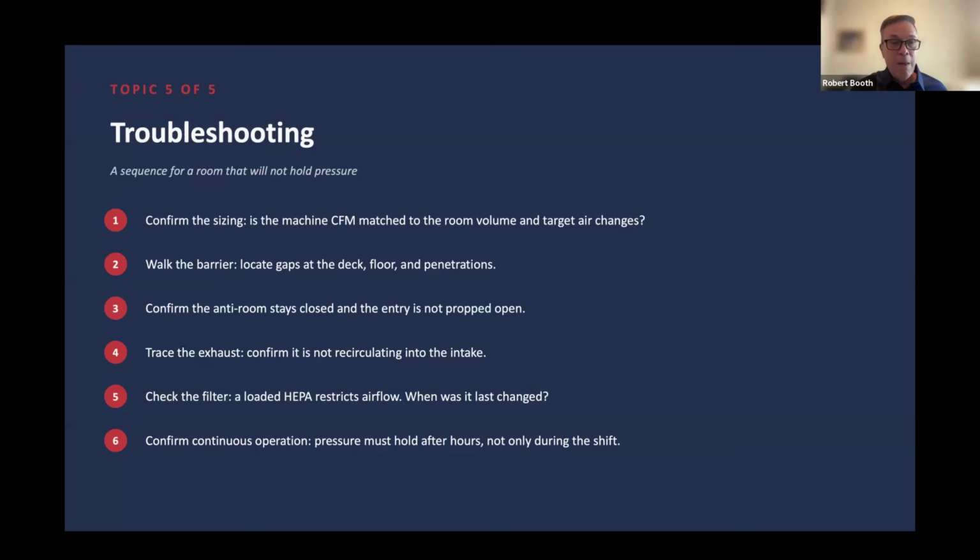The other thing I think happens a lot of times when we have a decrease in negative pressurization is people just don't understand that these machines can't be pushed around and pushed into other areas, and they start blocking them. Just like they do in ORs, they'll block them up, and all of a sudden you see a big piece of plastic got sucked into something, and it's a problem.